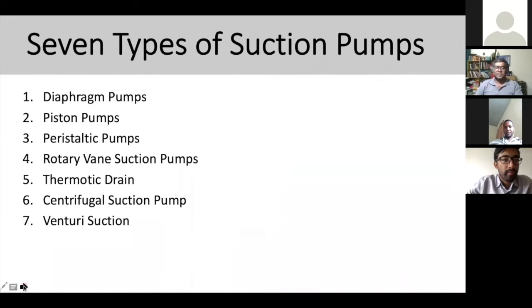There are seven types of suction pump that you should know: diaphragm pump, piston pump, peristaltic pump, rotary vane suction pump, Thermotic Drain, centrifugal suction pump, and venturi suction pump. These are the types of pumps you're going to see daily, depending on your hospital setup.